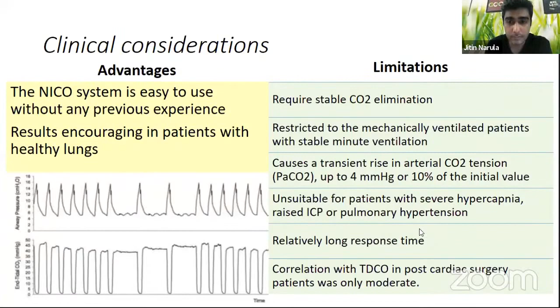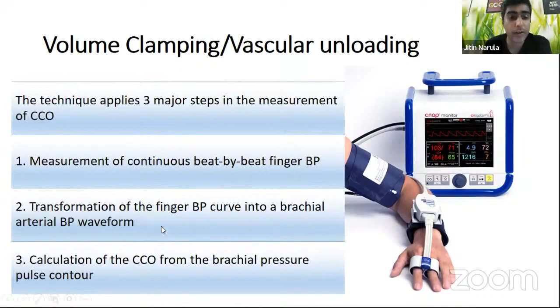Coming to the volume clamping or vascular unloading technique, it applies three major steps. First is the measurement of continuous beat-by-beat finger blood pressure, followed by transformation of the finger BP curve into the brachial arterial BP waveform, and calculation of continuous cardiac output from the brachial pressure pulse contour. The measurement of the continuous finger BP by photoplethysmography involves wrapping of a cuff around the middle phalanx. This finger cuff LED emitter detector measures the diameter of the finger arteries running on both sides of the palmar aspect. The cuff pressure is adjusted to keep the diameter of the finger arteries constant throughout the cardiac cycle by sending infrared signals. This is known as the volume clamp method.